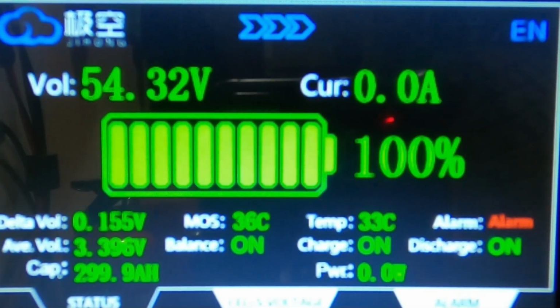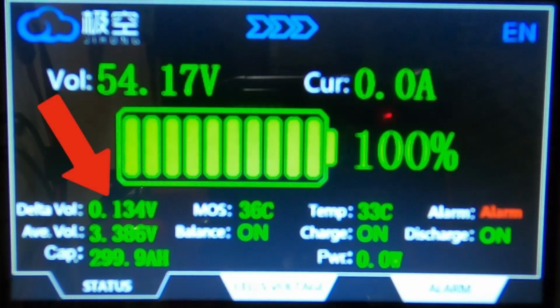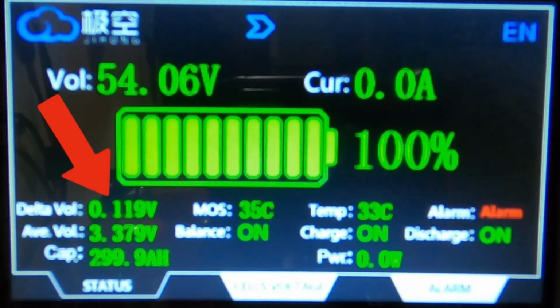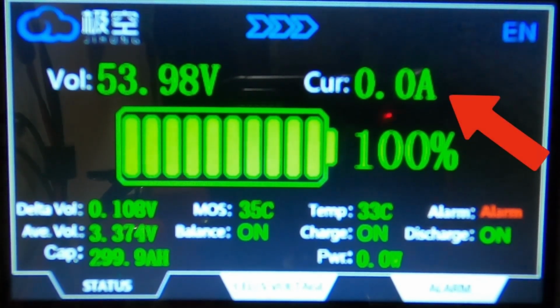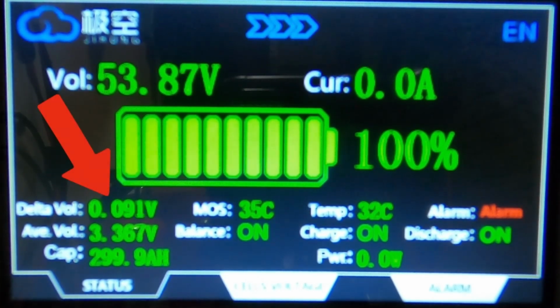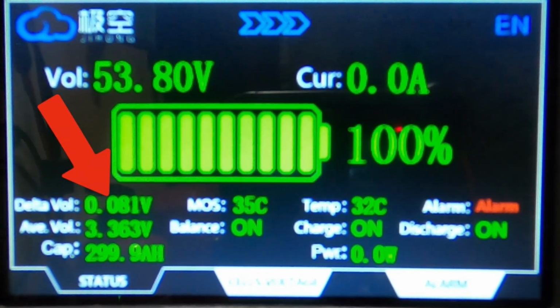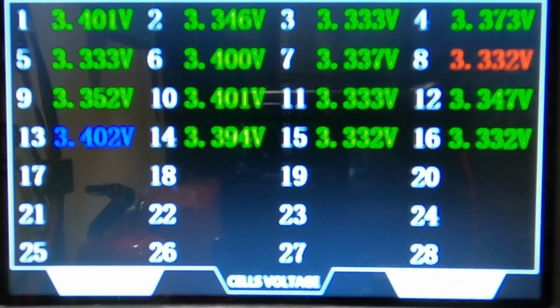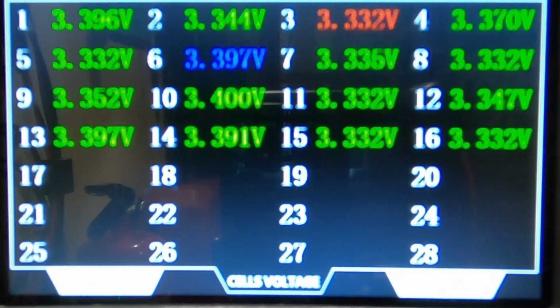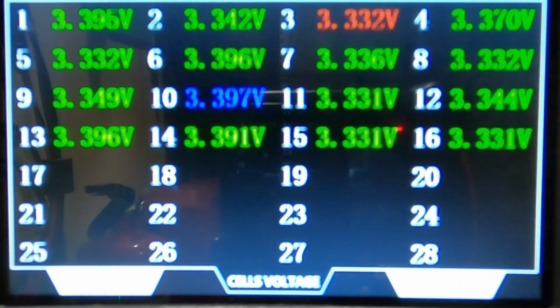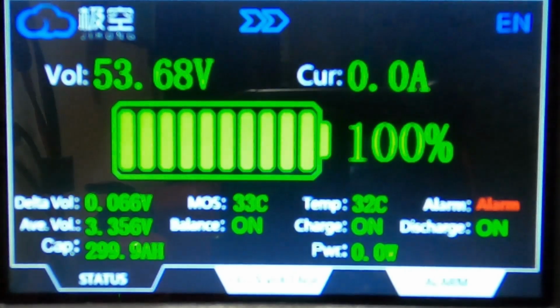So we started with a deviation of 230 millivolts. We can see here the BMS is working on the cells, trying to balance them out. Notice there is no charge current coming into the battery. We are balancing down only. Notice the delta. It gets smaller and smaller as the BMS balances the cells. The lower the delta, the more balanced the cells are. A good delta, in my opinion, is less than 50 millivolts when the battery is fully charged. In the bulk area or nominal voltage range, it is not uncommon to see 20 millivolts or less. Any discrepancies in cell deviation will be revealed at higher charge and discharge rates.